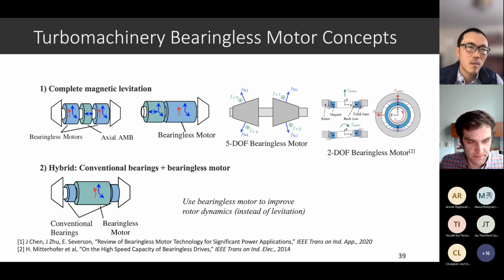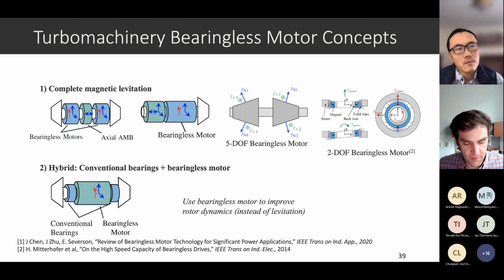One of the interesting things about magnetic levitation is that it opens up the possibility of letting your shaft intentionally have some orbit or some runout, some eccentricity. Sometimes we do this, especially in compressors, where it's maybe not so critical that your shaft be precisely centered. There are some clearances with the centrifugal compressor, but maybe it's okay if you have 100 microns of runout.